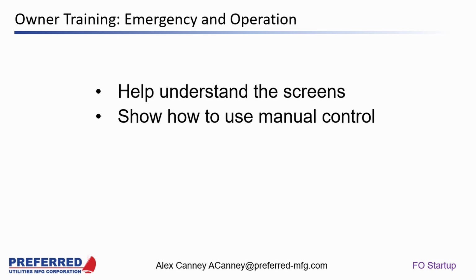And we see this as a basic industry standard for advanced controls for backup power and mission critical applications, where we can get some pushback on some of the newer systems, especially from facilities or engineers that are used to legacy systems. Okay, this has a computer in it now, right? And I know computers don't always work exactly the way we want them to. But that's a really good point that all of our systems have, and other systems should have, some way to bypass in manual mode all of the wonderful fancy electronics, if there's a program issue, gets hit by lightning or whatever, and to manually turn those motor starters on.